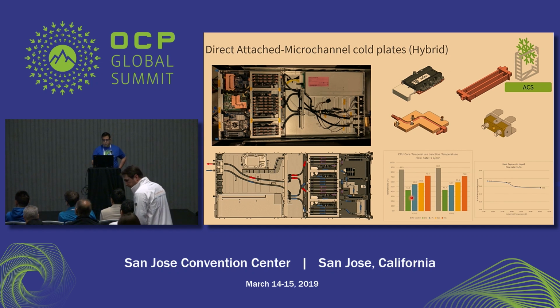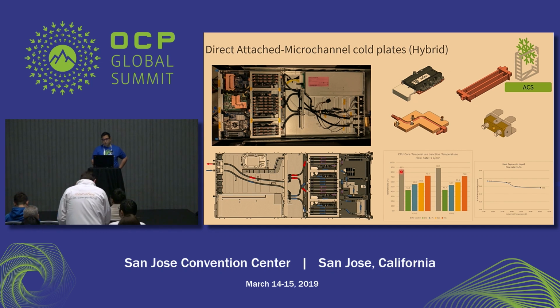The air-cooled unit is at 85 Celsius. When we implement the cold plates, at W1 we could bring the junction down to 43, and at W4 it could be 72. Those are the two ends of the spectrum: either enable more performance on the chip, or save on leaking current on the lower end, or go to the higher end and enable dry cooler operation. That's a decision to be made.